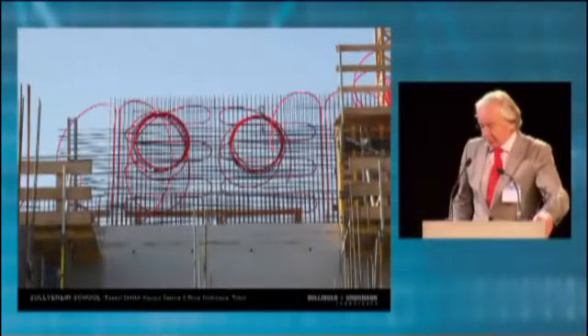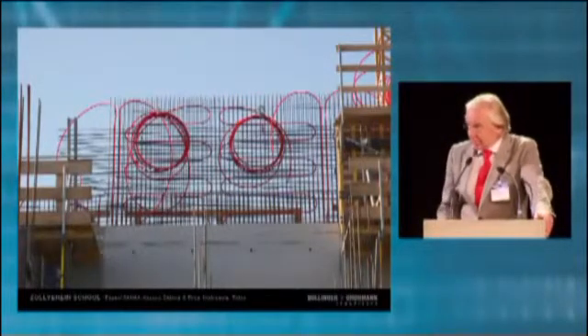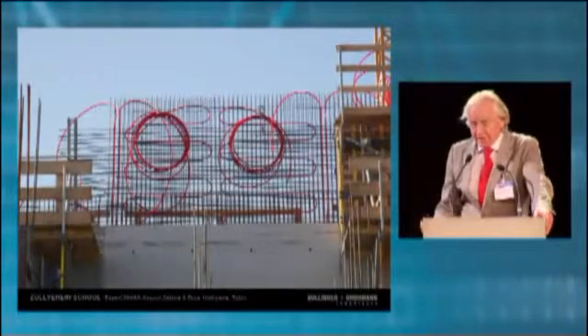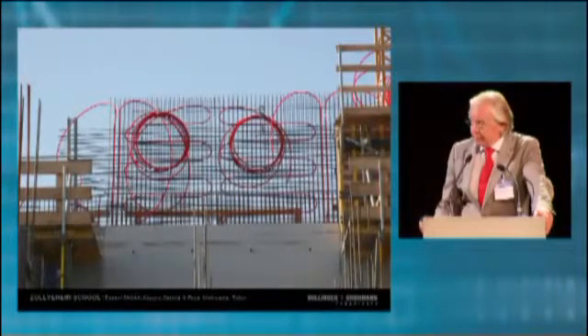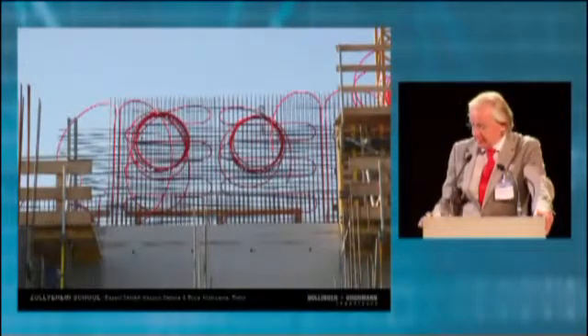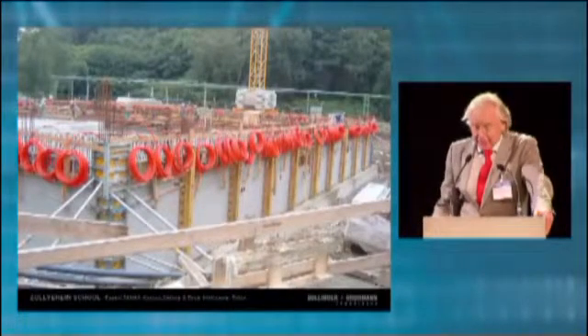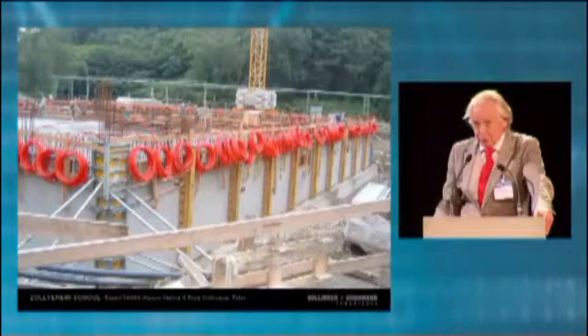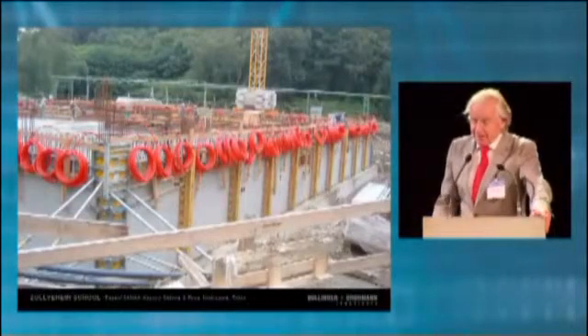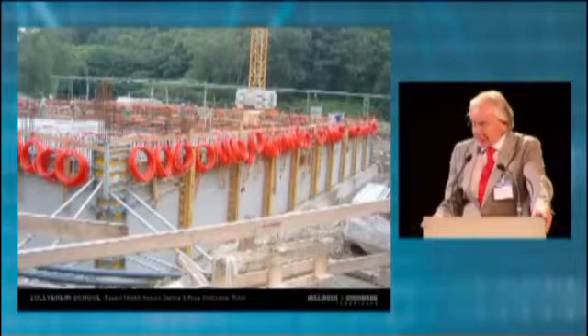And to reduce the thickness of the wall, we could use a technique that is quite unique and is only possible in this special area, since this is the area of a former coal mine, where they still have to pump more than 20 cubic meters of water with a temperature of 25 degrees per hour. And until this building, they just gave it away. We use these pipes to let this water flow through the exterior walls, and with this technique we completely eliminate the thermal losses of the building. In the planning team we call it active insulation.